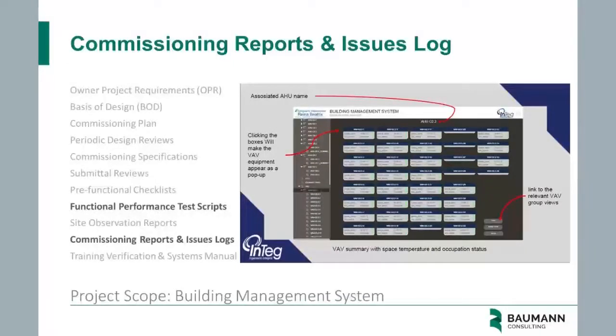And in real time, the gaps that you see under the VAVs are for the VAVs that haven't come online yet. It shows basically any space temperature, occupancy status of the different VAV boxes. It shows links to relevant VAV groups, and it shows associated AHU names, so you can always track back which AHU is feeding a VAV if it has a problem.